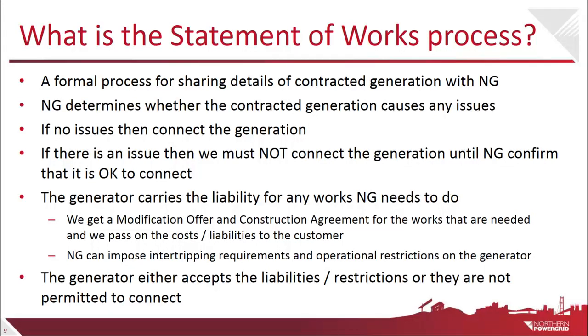Within those requirements, there could be an intertripping requirement or an operational restriction on the generator. The customer then has a choice: they can either accept those liabilities or restrictions, or they have to choose, in effect, to cancel their scheme because they're not permitted to connect.